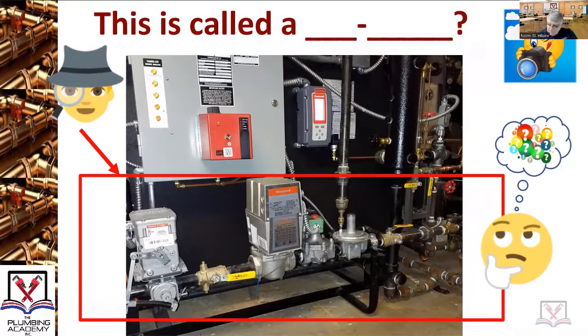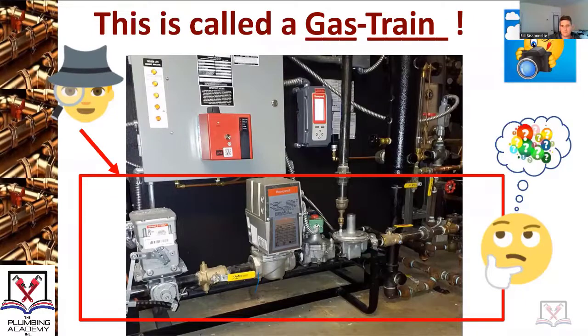This is called a gas train. As you look at a gas train like this and its components, at some point you're going to be able to tell — if you see a picture of this — how many BTUs the appliance is that this gas train is actually serving. Some things you may not know: when you have a vent off of a gas pressure regulator, how far it can go before it has to hit the outside of a building, based on the size.